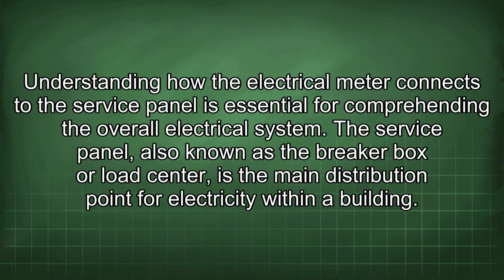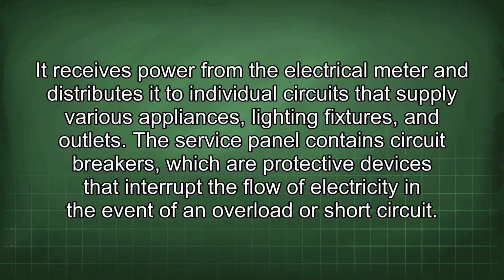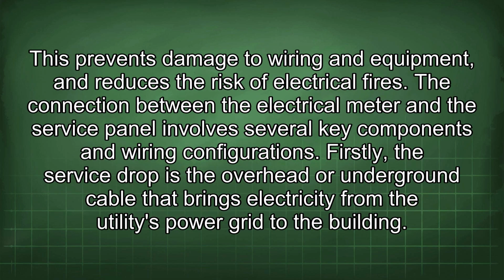The service panel, also known as the breaker box or load center, is the main distribution point for electricity within a building. It receives power from the electrical meter and distributes it to individual circuits that supply various appliances, lighting fixtures, and outlets. The service panel contains circuit breakers, which are protective devices that interrupt the flow of electricity in the event of an overload or short circuit. This prevents damage to wiring and equipment, and reduces the risk of electrical fires.